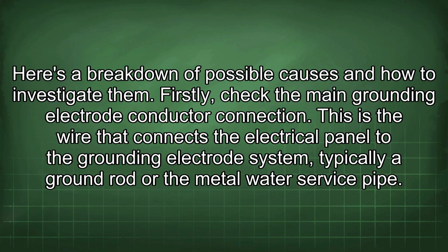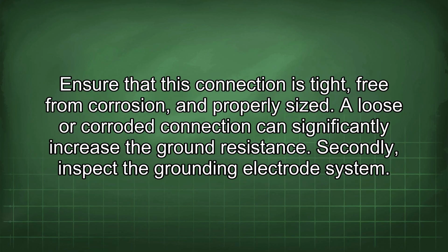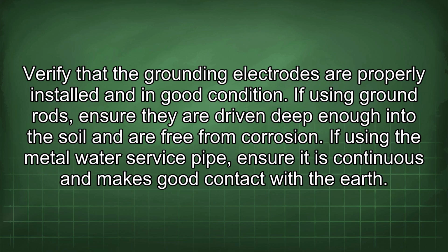Firstly, check the main grounding electrode conductor connection. This is the wire that connects the electrical panel to the grounding electrode system, typically a ground rod or the metal water service pipe. Ensure that this connection is tight, free from corrosion, and properly sized. A loose or corroded connection can significantly increase the ground resistance. Secondly, inspect the grounding electrode system. Verify that the grounding electrodes are properly installed and in good condition. If using ground rods, ensure they are driven deep enough into the soil and are free from corrosion. If using the metal water service pipe, ensure it is continuous and makes good contact with the earth.